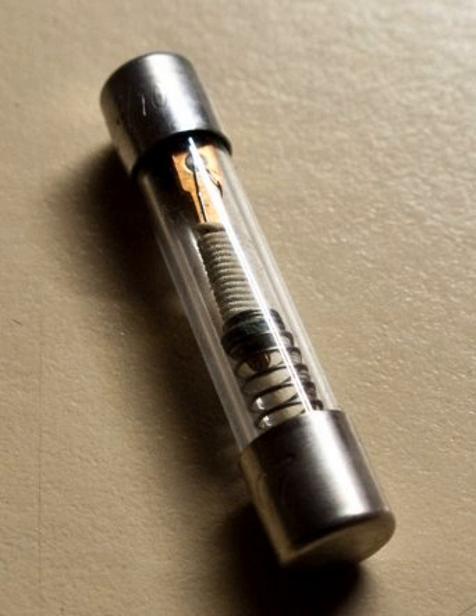Topic: Expulsion fuses. Large power fuses use fusible elements made of silver, copper or tin to provide stable and predictable performance. High-voltage expulsion fuses surround the fusible link with gas-evolving substances, such as boric acid. When the fuse blows, heat from the arc causes the boric acid to evolve large volumes of gases. The associated high pressure, often greater than 100 atmospheres, and cooling gases rapidly quench the resulting arc.